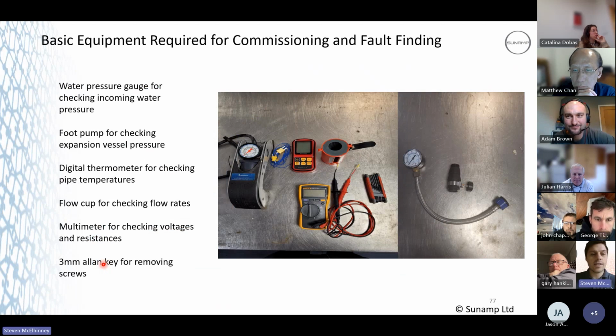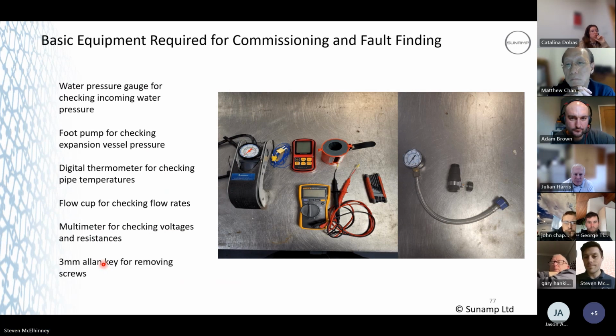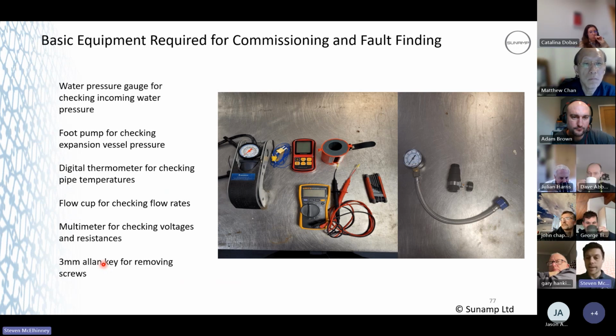Silence is golden. So your basic equipment for commissioning and fault finding. That's all you're ever going to need for working on a heat battery. Maybe a terminal screwdriver at some point if you're replacing a temperature sensor, which is a 2mm flathead for removing the screws. But initially, a water pressure gauge for checking water pressures, standing pressure and working pressure.